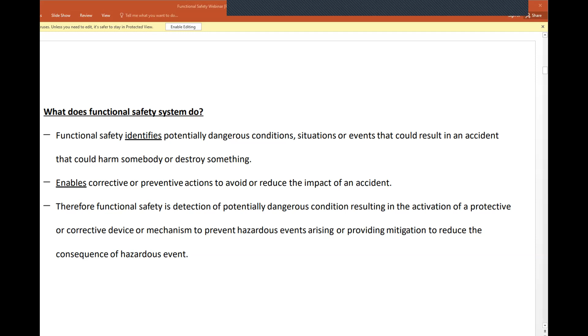So how do I prevent this? I need an automatic protection system. How do I do that? An automatic protection system, which again has a sensor and an electronic controller, which operates the valve, means it closes the valve or switches off the motor. It does both things. If the level reaches the sensor in the red color, then it switches off, independent of the man's action. It's presumed that the man will act, but suppose he doesn't act, the sensor will detect the fluid level and switch off the motor. So this is a functional safety system. It has a sensor and a controller. These are the components of a functional safety system: input, processing, and output. Any automatic protection system will have this. So this is a simple example of a functional safety system.